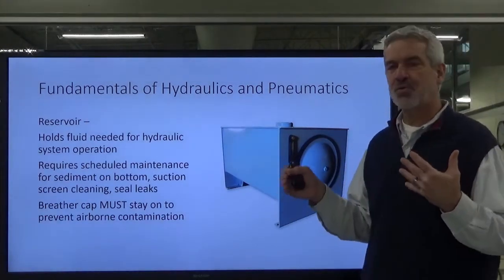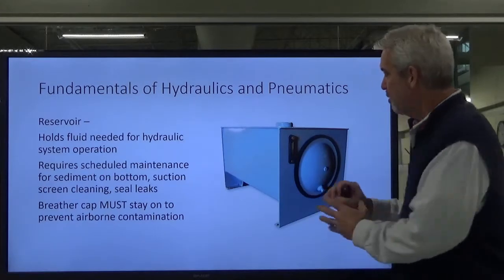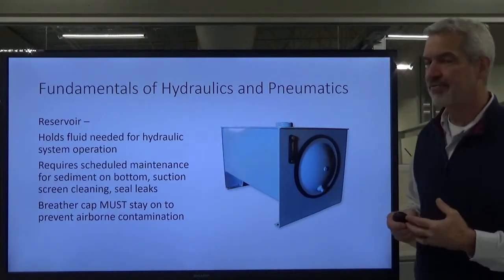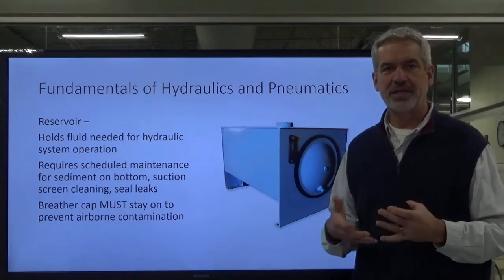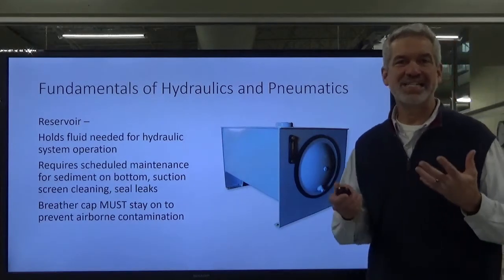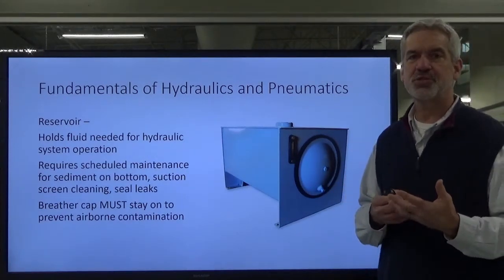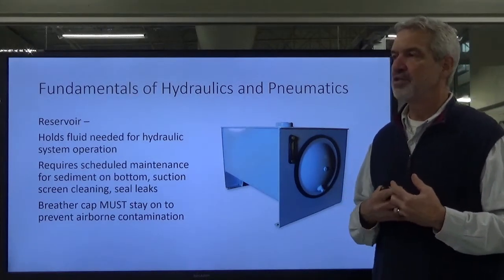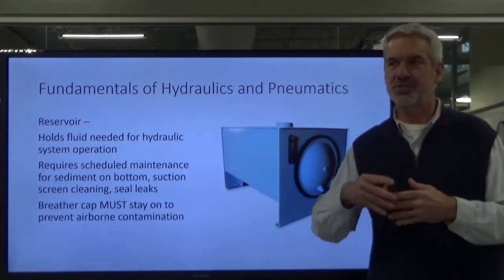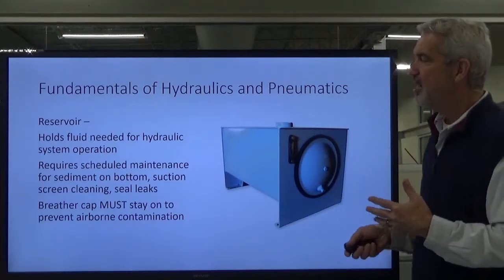This dirt gets to traveling in the system. It winds up landing in the bottom of our tank. We open up our tank and we've got sediment on the bottom. If the sediment builds too high, then the suction screen and hose on the pump side will start to suck that sediment up and run it through the system. Again, it requires maintenance. We've got to take it apart. We pull this apart. Our access cover right here, we pull it off after we've drained it out, and we usually clean it up on the inside.